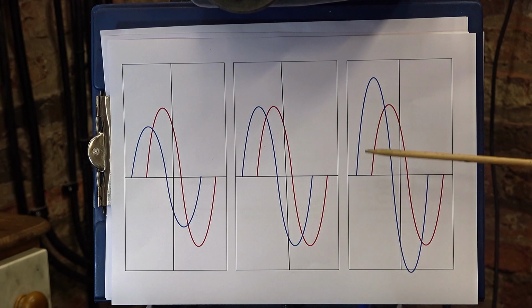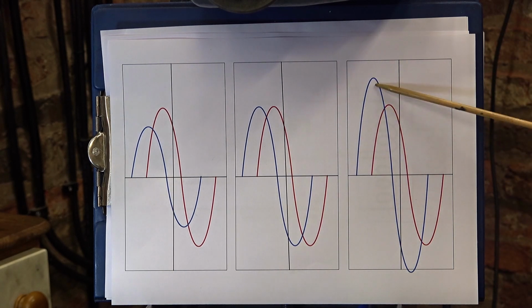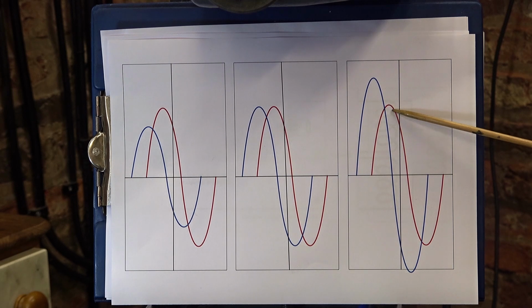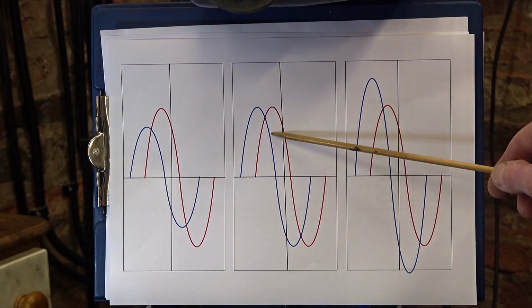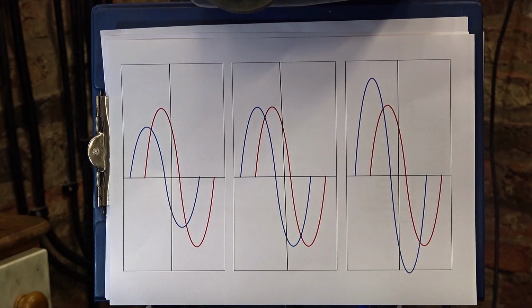What happens is when the relay clicks over and the start capacitor drops out and we run on just the run capacitor, this wave drops to this level. It looks more like this, and that tells us that our run capacitor is the right size. You'd be surprised when you see it just how close this is.